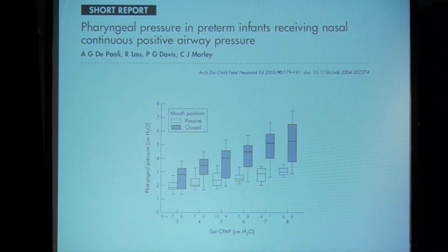And actually there was a study done in neonates in 2005, and this is with CPAP, but I'm sure it's the same thing with NIPPV, that when you look at a set level of assist in these babies and compare it to the pharyngeal pressure, you can see here whether the mouth is closed on purpose by a chin strap or if it's passively open, that there's a tremendous pressure loss. So let's say you're aiming to give 6 centimeters of water, you're only getting 4 in the pharynx. So what you're reading on the ventilator as that pressure is not necessarily what's going to the lung. I don't know what it is in a premature baby yet, but you should think about that.